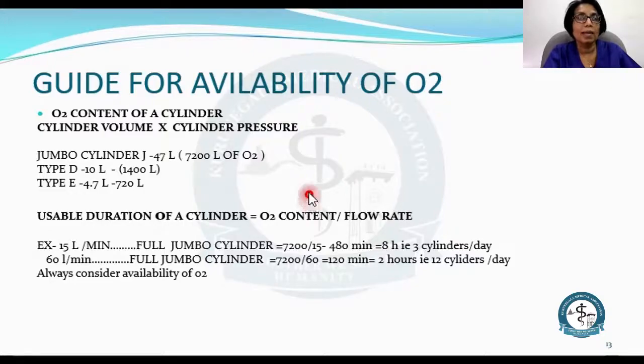So how long can each of these cylinders be used? For example, how do you calculate it? Usable duration of a cylinder is the oxygen content divided by the flow rate. So, for example, if you use oxygen at a flow rate of 15 liters per minute, a full jumbo cylinder can last only 480 minutes. That means 8 hours. So, to provide a man who needs 15 liters of oxygen per minute, we need 3 jumbo cylinders a day.